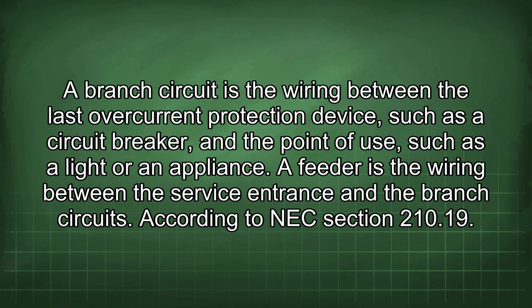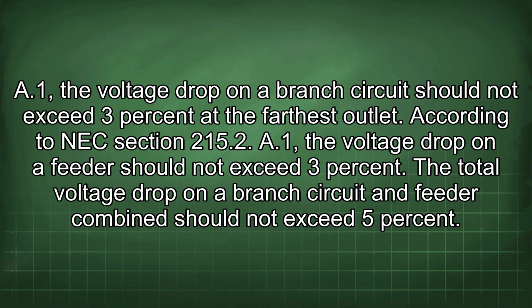According to NEC section 210.19(A)(1), the voltage drop on a branch circuit should not exceed 3% at the farthest outlet. According to NEC section 215.2(A)(1), the voltage drop on a feeder should not exceed 3%. The total voltage drop on a branch circuit and feeder combined should not exceed 5%.